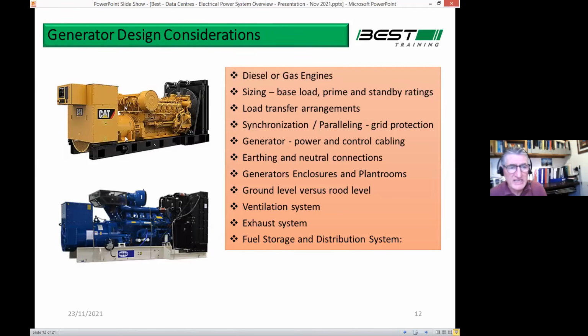Right, so we're going to start looking at a few of the other components on the system now. Generators obviously play a huge part in data centers, and as I said, we were informed in the Irish Times this morning that it's now going to be mandatory, but of course, you take it as read. Every data center has backup generators anyway. They weren't waiting on EirGrid to advise them to put them in. The big difference is EirGrid will now be able, by law, to force them to come off the grid and go onto their standby power, whereas at the moment, they've no obligation to do that.